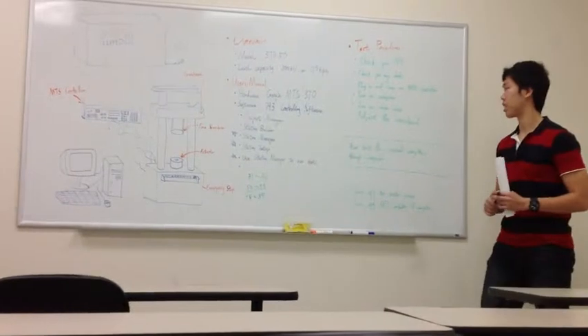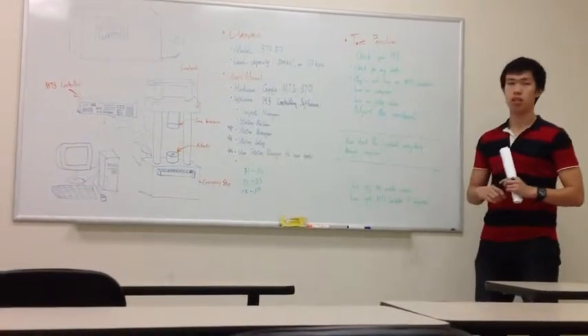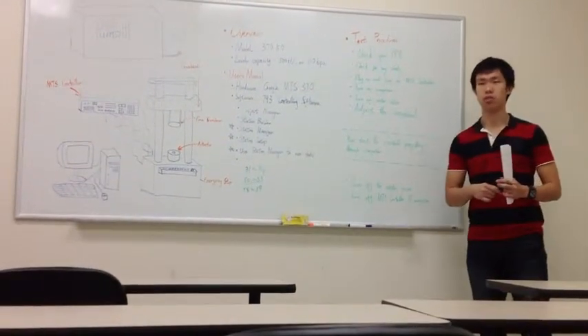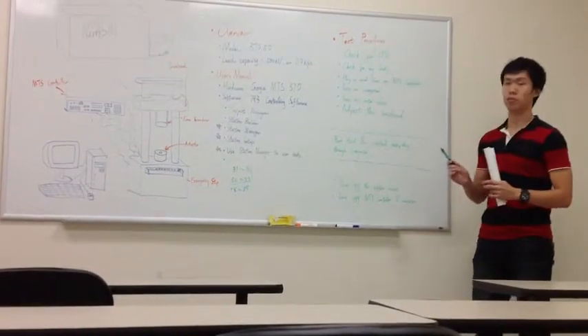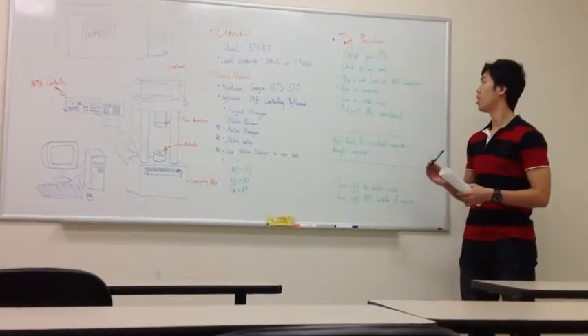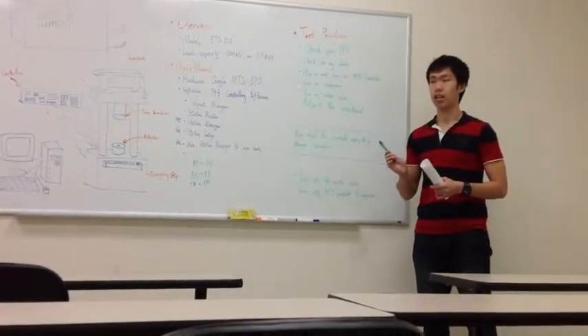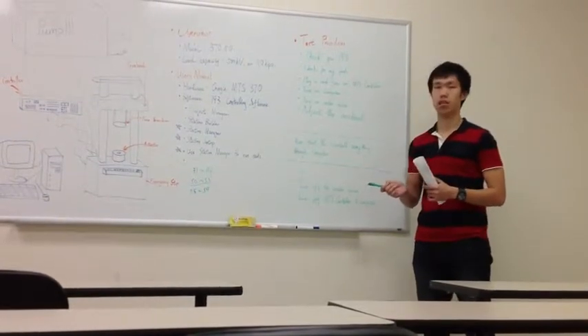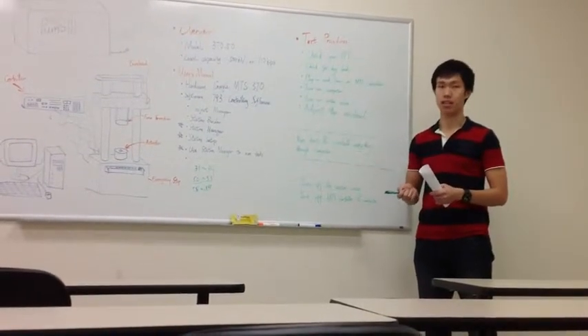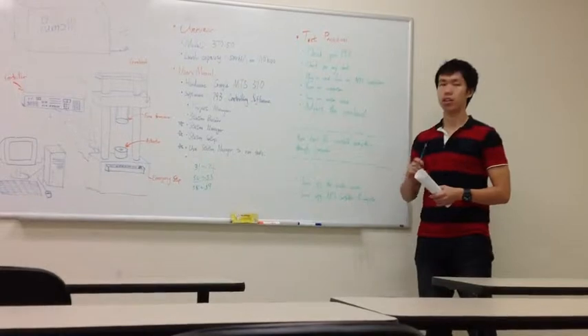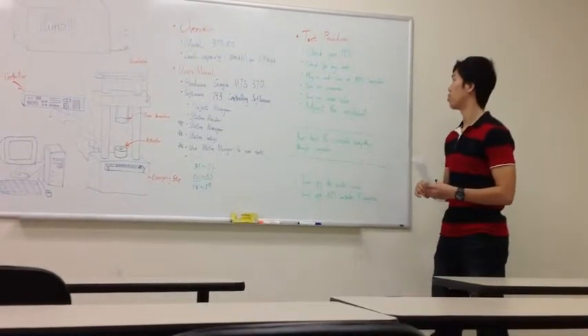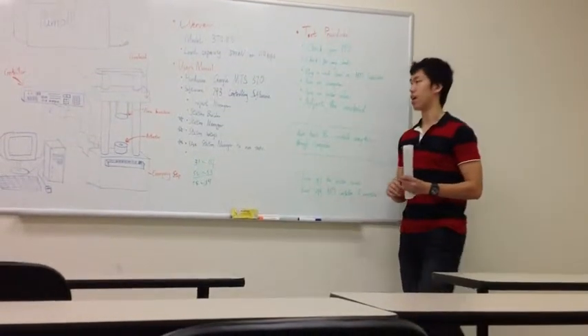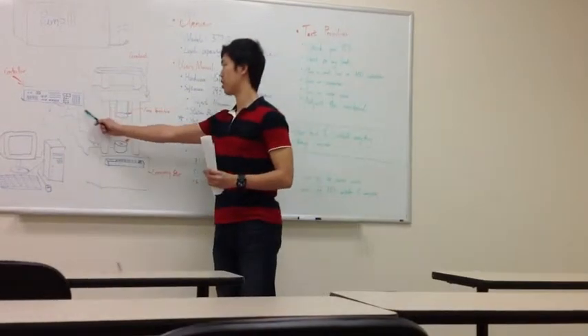So let's go to the test procedure part. Before you run the test, you will need to check your personal protective equipment. Then you need to check for any leaks, because any leaks in the pump area will be really dangerous. And after all the checks is done, make sure you plug in the wires and turn on the MTS controller, which is this thing.